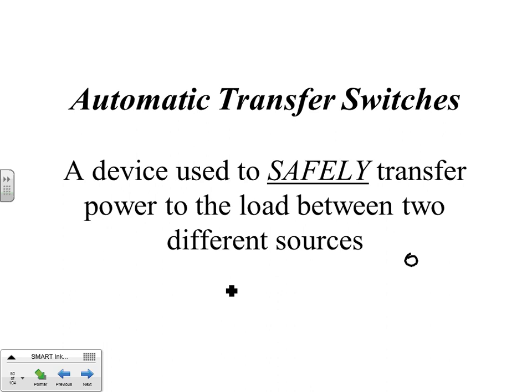Most common transfer switch, and we're going to see some of my drawings here in a minute. This is the load down here. This would be normal power here, emergency out here. What a lot of people have done in the past, before we had codes that said you've got to be careful with this, is they would do things down here. When the power failed, normal went away, they would say, well, I can feed this in on a circuit breaker in my panel and backfeed the whole panel. Not a good idea. So a transfer switch will allow you to, when the power fails, start the generator set.